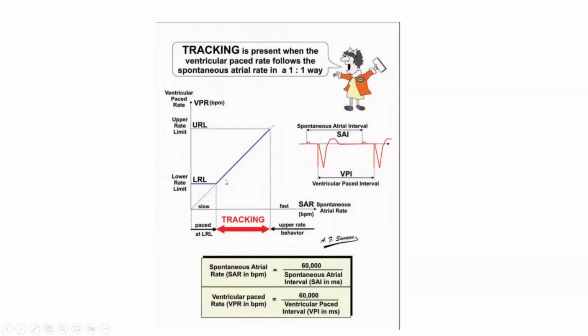If I have a normal sinus node function, the sinus node rate will increase if the patient is exercising or is anxious. And this increased sinus rate will drive the heart rate to increase until I reach the point of the total atrial refractory period. Remember, what's the total atrial refractory period? The pacemaker can handle one P wave at a time. One P wave, he gets a QRS complex for this, and he is ready to receive another P wave.